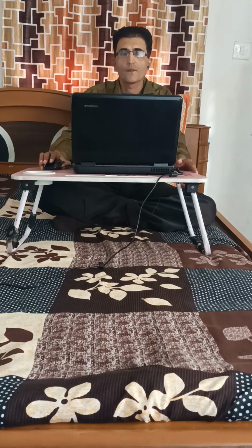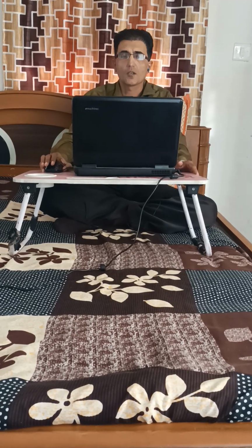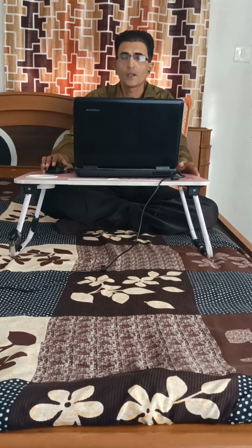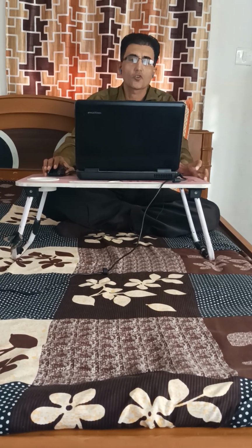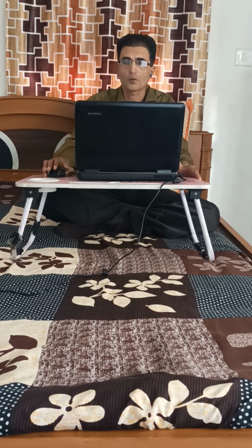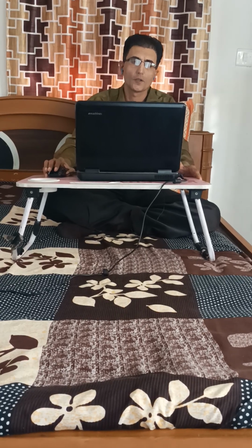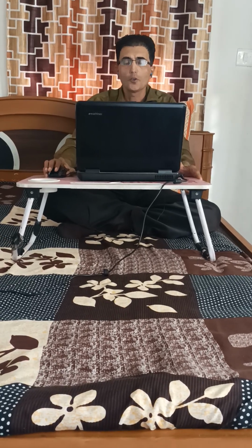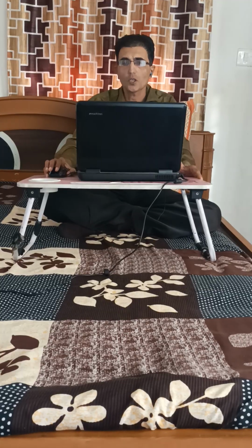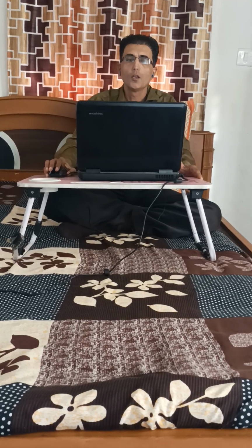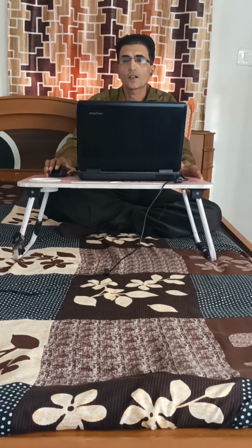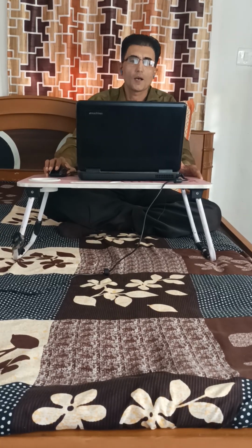Furnace: in the furnace, combustion occurs. It is the place where the highest temperatures in the boiler are reached. Furnaces are usually corrugated to increase the mechanical strength, although non-corrugated furnaces are not uncommon. Tube seat: tube seats are used to seal both ends and provide a place for mounting tubes. Tube seats are usually connected to the shell via stay bars.